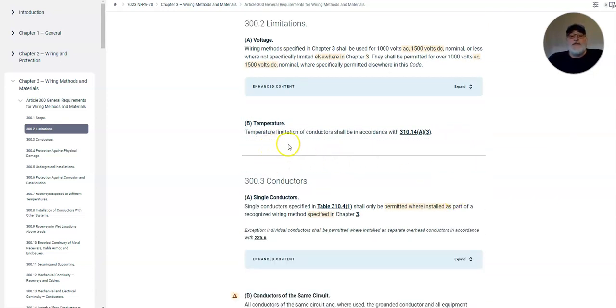Temperature, okay? Temperature limitation of conductors shall be in accordance with 310.14(A)(3). Temperature is our nemesis. Whenever you run a current through a wire, the magnetic field that it creates, the movement of the conductors or the movement of the atoms itself as they go through will actually generate heat. That's why we have limitations on how many wires we can put into a pipe. That's why we have a limitation on the insulation of the conductors themselves, because heat dissipation is a requirement. Otherwise, what happens if you get a lot of something in a small area and it starts heating? What you end up with is thermal breakdown. You end up with the jackets or the insulation on the conductors themselves breaking down, and you start having failures. That's where you get fires. That's where you cause damage to structures.